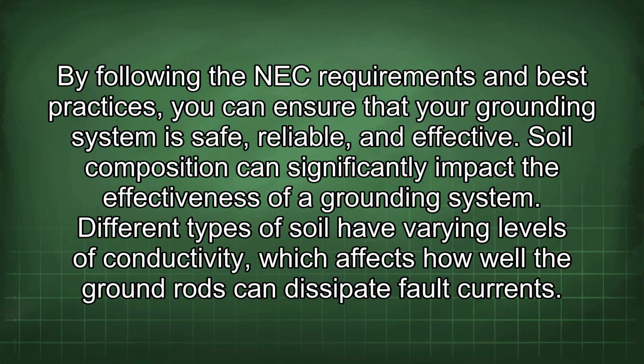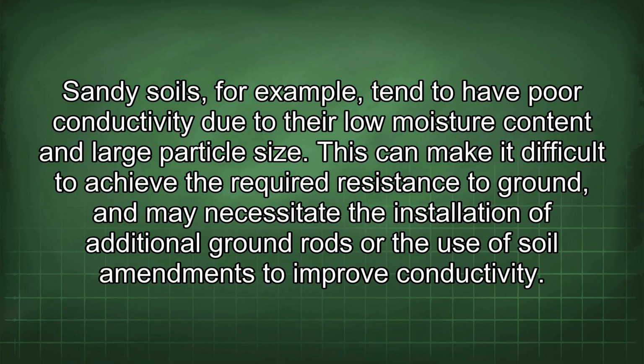Soil composition can significantly impact the effectiveness of a grounding system. Different types of soil have varying levels of conductivity, which affects how well the ground rods can dissipate fault currents. Sandy soils, for example, tend to have poor conductivity due to their low moisture content and large particle size. This can make it difficult to achieve the required resistance to ground, and may necessitate the installation of additional ground rods or the use of soil amendments to improve conductivity.